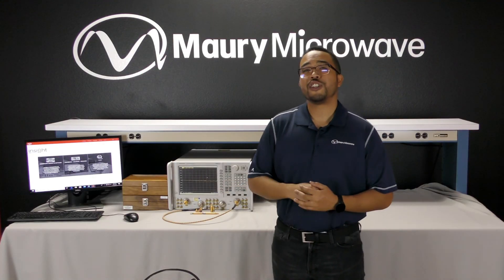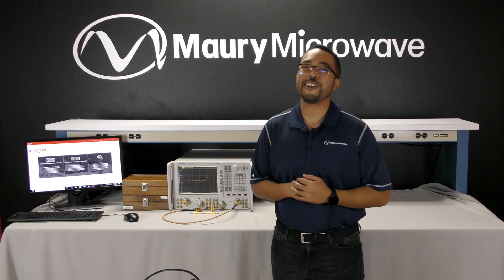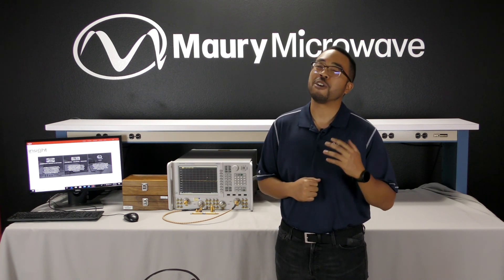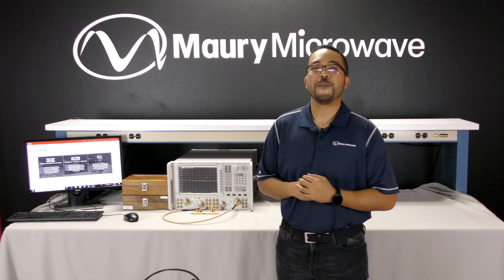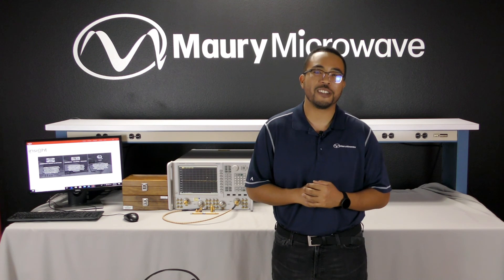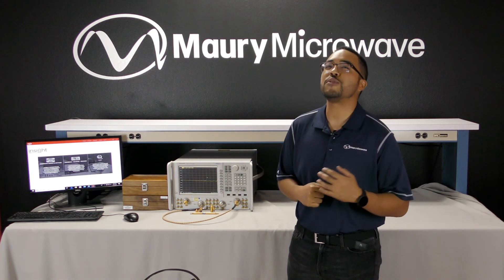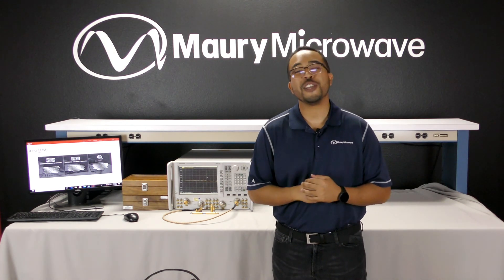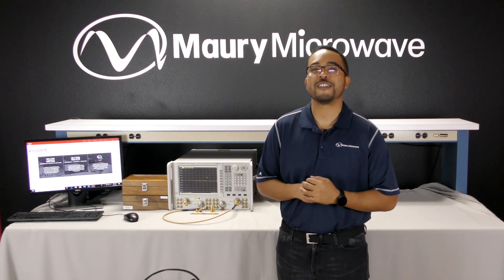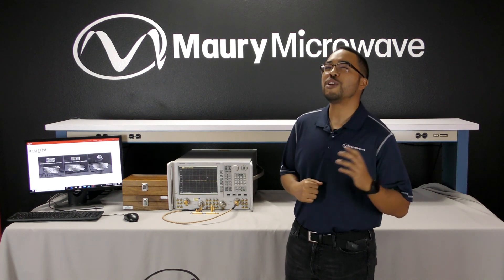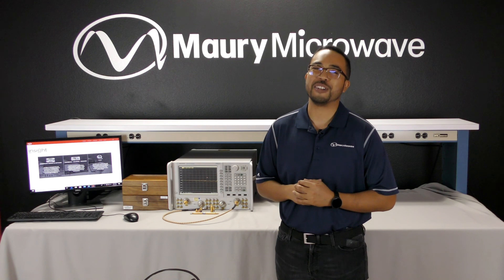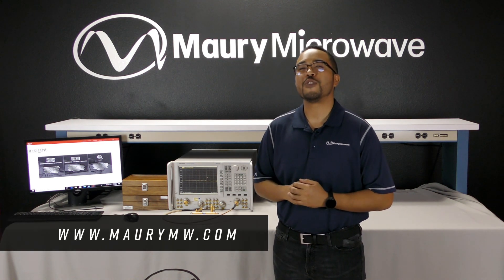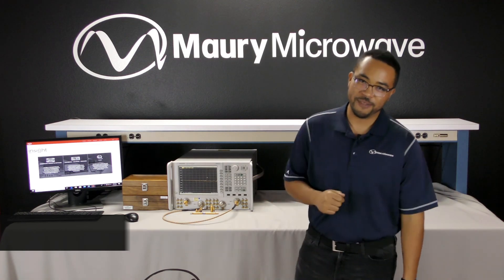As we showed in our demonstration, using shareable standardized calibration project files will help ensure you are calibrating your VNA the same way every time across all VNAs and ensure consistent measurements. Furthermore, we have improved the calibration validation process, replacing ambiguous and subjective source match validation with individually characterized standards that mimic your device under test. Finally, by using measurement uncertainties with our validation process, we can use normalized error to determine definitively when the calibration is good or needs to be redone, therefore leading to increased confidence in your measurements. For more information regarding Insight, please visit maurymw.com. Thanks for tuning in.